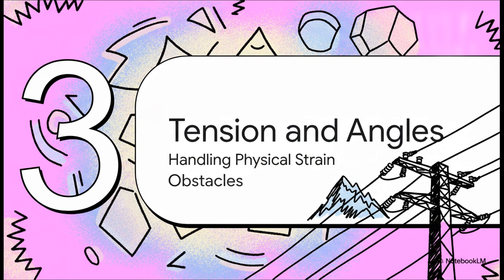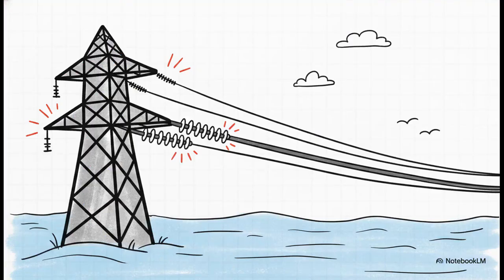All right, part three, handling tension and angles. The crucial point is that when a power line has to abruptly stop, turn a sharp corner, or cross a massive gap like a river, the physical strain on the line is off the charts. Enter the strain insulator. Its applications include dead-end towers, river crossings, and sharp angle towers. Physically, it looks a lot like the suspension insulator we discussed earlier, using those same basic disc units.